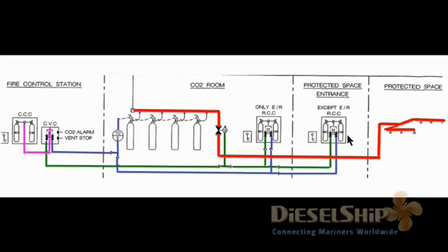Remember, when you're operating from the engine room entrance, somebody has to go to the fire station or the emergency station, from where you have to shut the quick closing valves, and do the emergency stops of blowers, pumps, dampers, everything. Or if this arrangement is there, you must be capable of shutting the quick closing valves and everything just outside the engine room. All arrangements must be nearby.